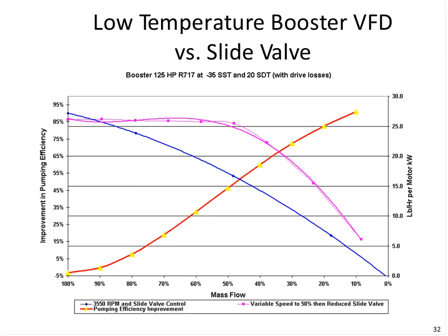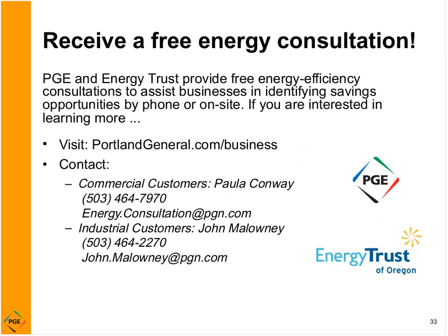Here's another slide portraying the low temperature applications. So here we're using ammonia as a refrigerant, at minus 35 degrees. Here's the slide valve and its impact on efficiency, and then here's the variable speed. And notice the variable speed, down to about 50%, sustains a fairly even efficiency, where the slide valve has a degradation of efficiency, and at some point here we're seeing as much as 50% energy savings. Very interesting, especially where we have significant time at part load.